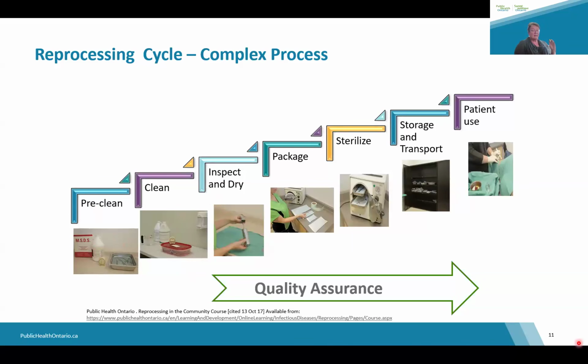Next, we have cleaning. And cleaning in the reprocessing area can be done either manually using scrubbing followed by the use of an ultrasonic cleaner, or you can do it in an automated way using a washer disinfector. And this is dependent upon your situation. But the important thing is instruments have to be scrupulously clean because we cannot sterilize through dirt. So after cleaning, you rinse, because you need to make sure that you rinse off the cleaner that you used. If you had them sitting in an ultrasonic cleaner, then you take them out, the particles that are suspended in that solution may stick to the instrument again. So you need to rinse that off. So you're going to rinse it and you're going to dry it with a low linting cloth before packaging. And this is really a good opportunity to inspect your equipment and to lubricate it and ensure that they have been cleaned properly and that they're still functional.